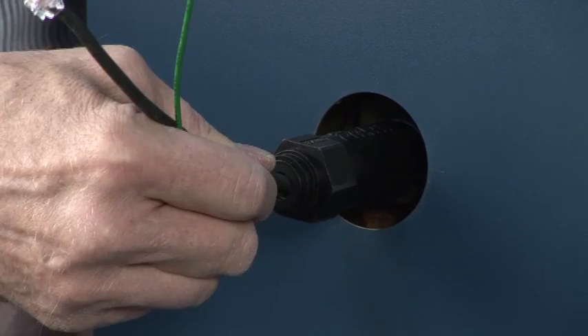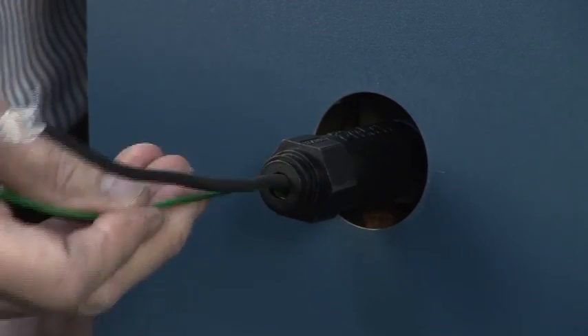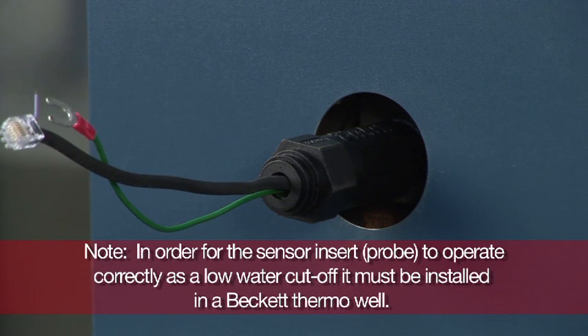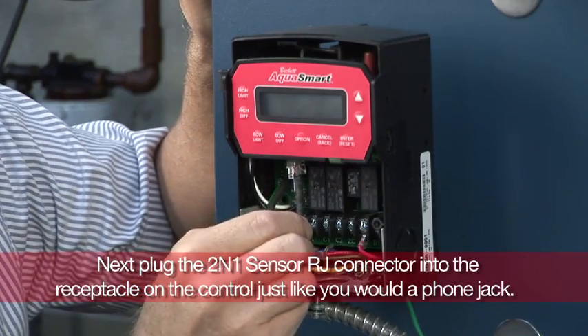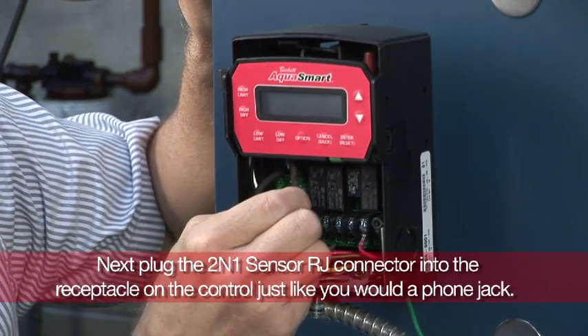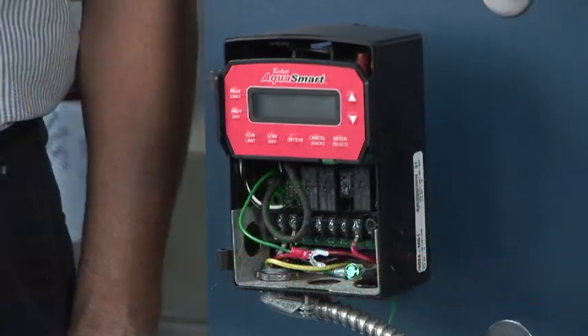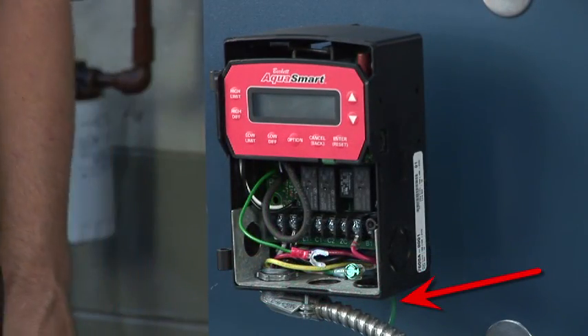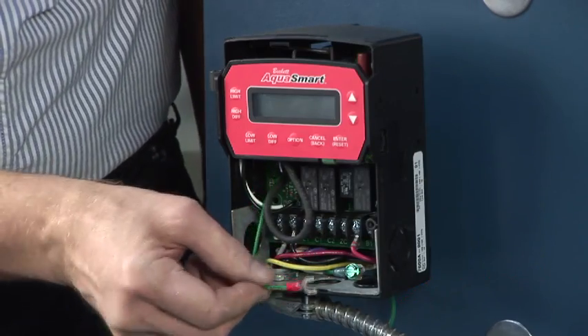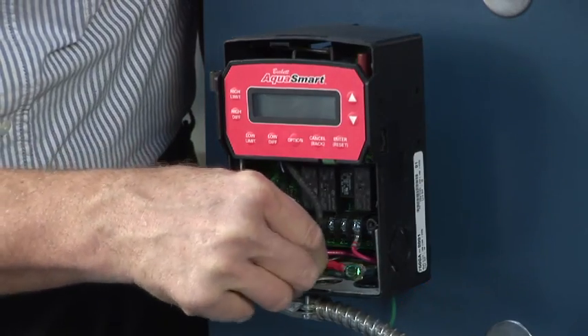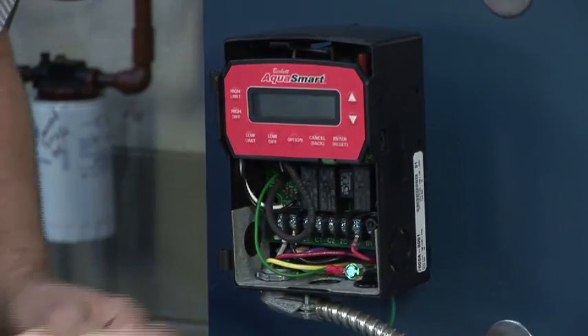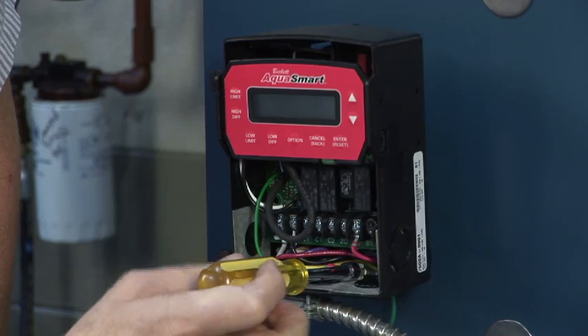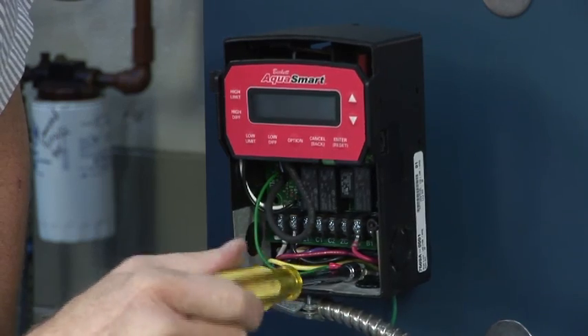Now route the sensor leads through the control opening and securely install the control onto the thermowell. Note, in order for the sensor insert probe to operate correctly as a low water cutoff, it must be installed in a Beckett thermowell. Next, plug the 2-in-1 sensor RJ connector into the receptacle on the control, just like you would a phone jack. Now route the 36-inch green wire through the bottom rectangular slot on the AquaSmart. You'll need to securely install the fork connector of the 36-inch ground wire and the green ground wire from the 2-in-1 sensor under the ground screw at the bottom of the control.